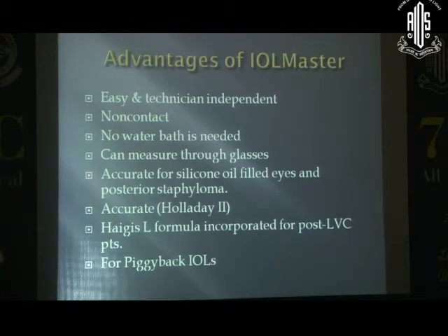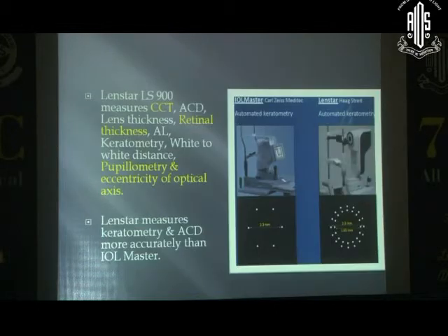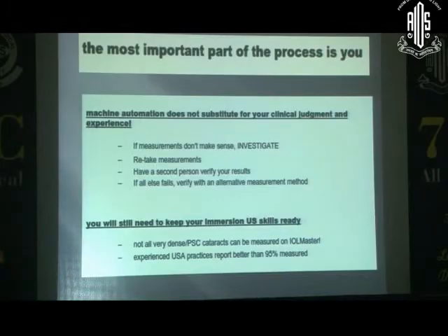The advantages being they are easy and even a technician can do it if trained properly. There is no contact, so no chances of transmitting infection. No water bath needed. Can measure through glasses also. It is accurate in silicone filled eye and with the Holladay 2 formula as well as Haigis, and even for piggyback IOL it is important. As I told you, when you are going for K readings, LenStar is theoretically slightly better than IOL Master.